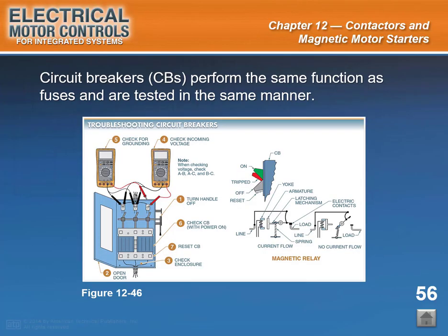Slide caption: Circuit breakers, CBs, perform the same function as fuses and are tested in the same manner. See figure 12-46. A circuit breaker known as CB is an overcurrent protective device with a mechanism that automatically opens the circuit when an overload condition or short circuit occurs. CBs are connected in series with the circuit and operate much like a relay. They protect a circuit from overcurrents or short circuits.